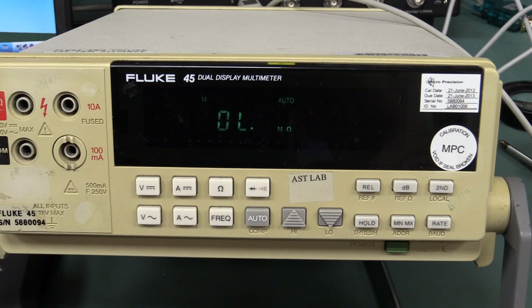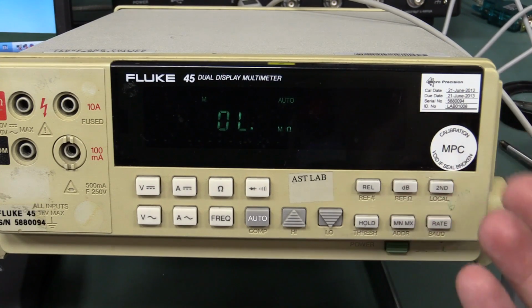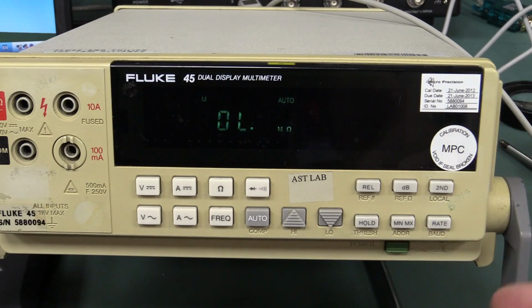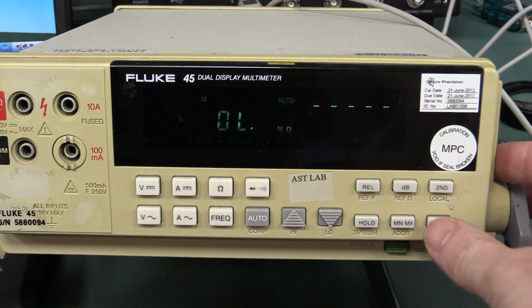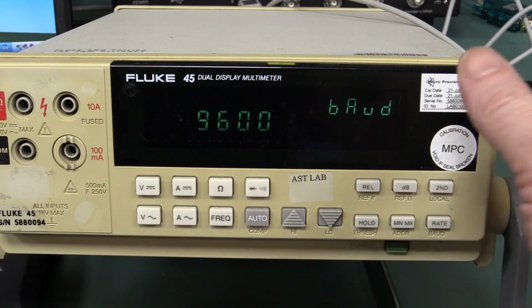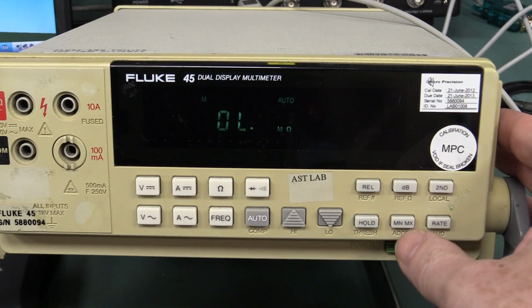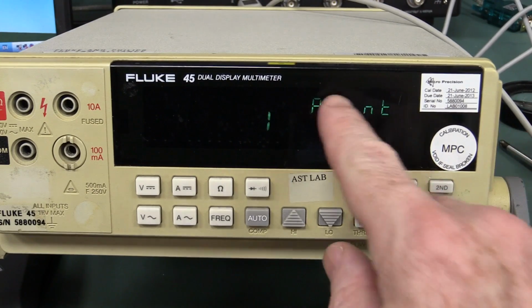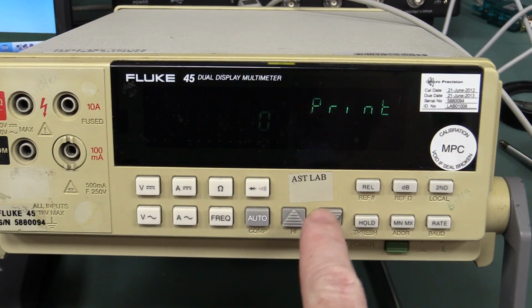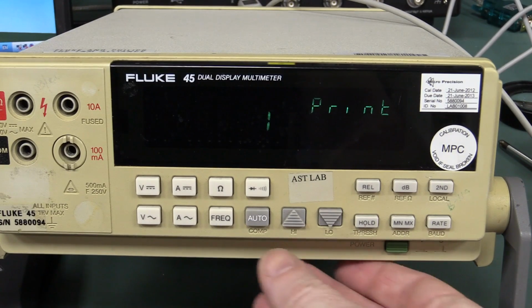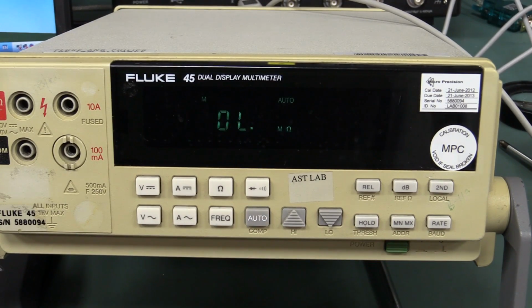And one of the really nice things about this meter is the serial output, as I said, but you can put it into what's called print mode. I mean, you can go into rate here and set up your baud rate and your parity and everything else, right? That's all normal. You go into second address here and you can go into print mode, and what that does is it actually outputs, this is how often it actually outputs data. We'll set this to 1 and you select auto there, and bingo, it's designed to output directly to a serial printer, or in this case, I've got a serial terminal hooked up.